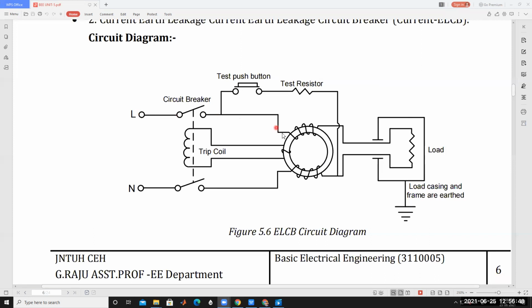The current enters the phase wire, goes through the current transformer, flows through the load and comes back the same way. So these are all connected in series with the load. If any fault occurs, for example a leakage here, the current is diverted to the ground instead of flowing to the neutral. Fault leakage current is nothing but a fault between load and earth. That is called earth leakage.